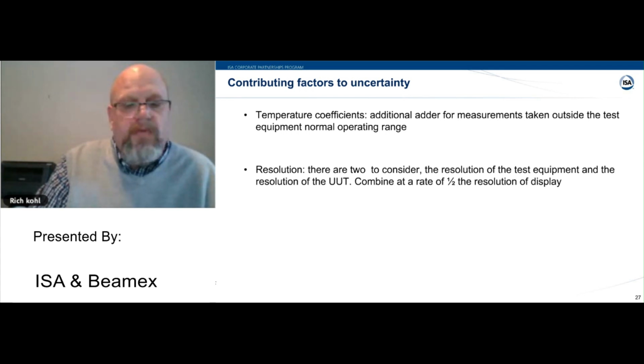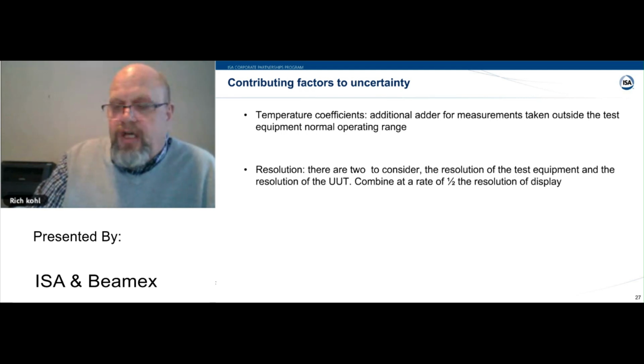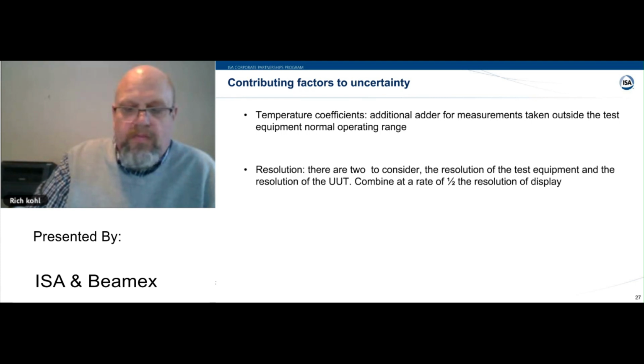So the next item here is resolution. There are two to consider: the resolution of the test equipment and the resolution of the unit under test. And we combine that at a rate of 1/2 the resolution of the display. So in the case of Roy's demo, his pressure module had a display reading of 0.0 or 0.1. That would be added in as a contributing factor at a rate of 1/2 of that lowest resolution, or 0.05 of whatever the engineering scale is that he's using.